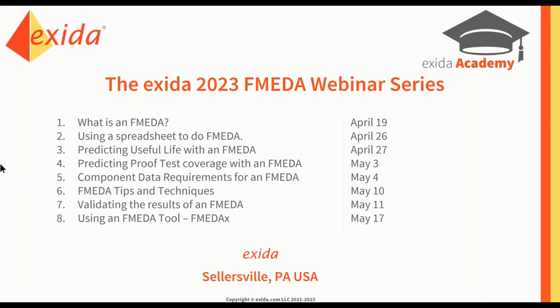But if you're guessing, you're going to have to make a conservative guess. If you're guessing it's going to be 25 years, back it off to 20 for purposes of your maintenance schedule. And then call your favorite vendor and tell them you really do expect this kind of information as they move forward. I've seen many of them start publishing this information as a function of time.